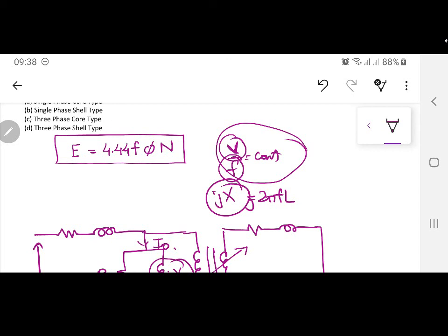See, when it's a low voltage winding, it's going to have a larger current rating. When a larger current rating is required, it will be thick. This is a high voltage winding. If you look at this one side, you can see this wire is very small, the cross-sectional area I am talking about is very small. And I hope you can also see this one, so this one is thick. So this is certainly the low voltage winding. It has a high current rating.